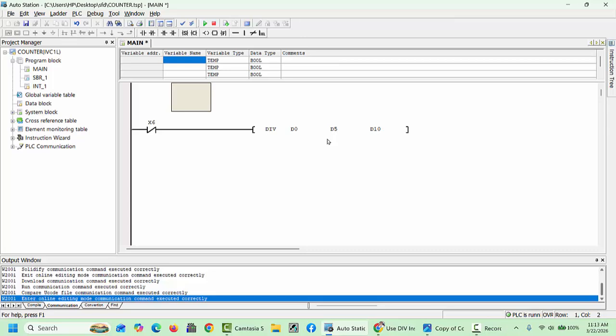To display this value in units like degrees Celsius or bar, you must use math, meaning the division instruction. For example, if a sensor gives a value of 10,000 for 100 Celsius, you would divide the raw value by 100 to get the actual temperature.